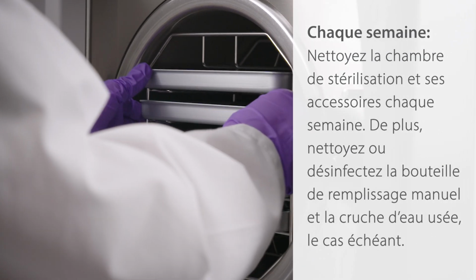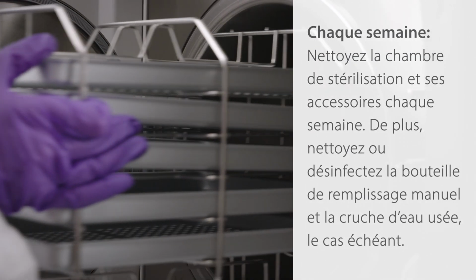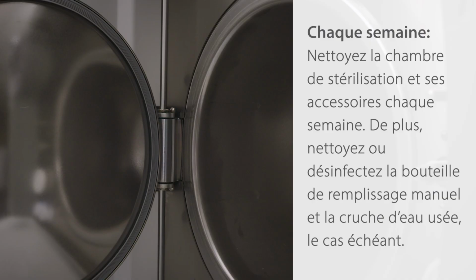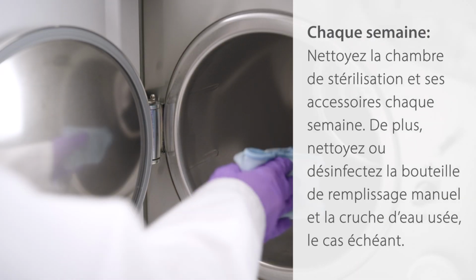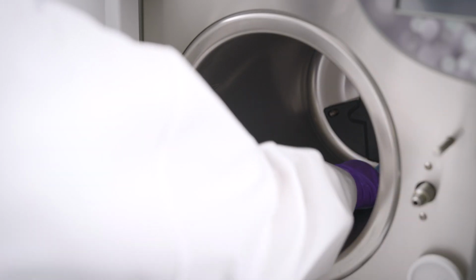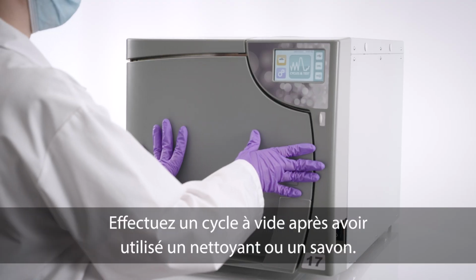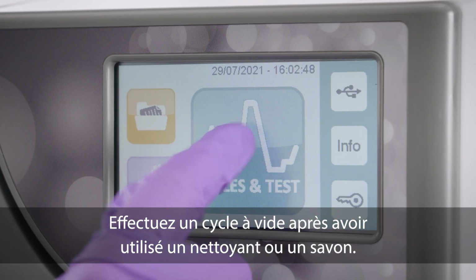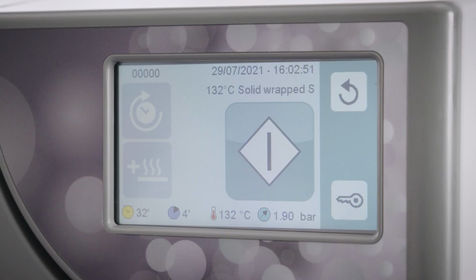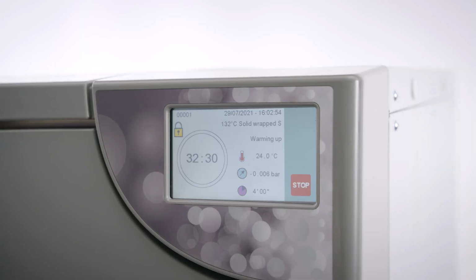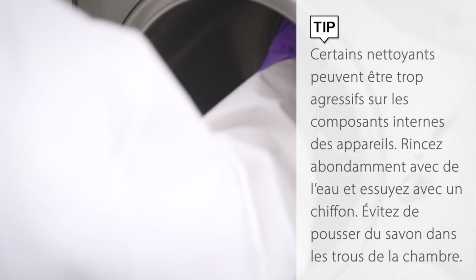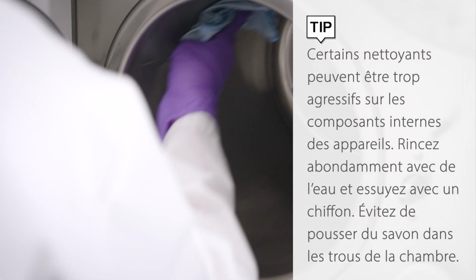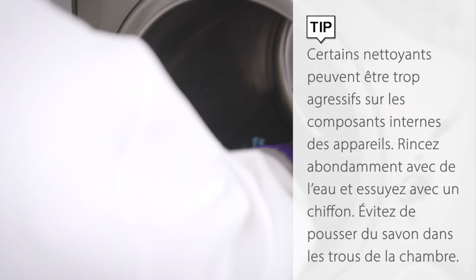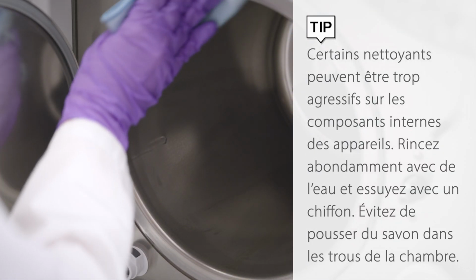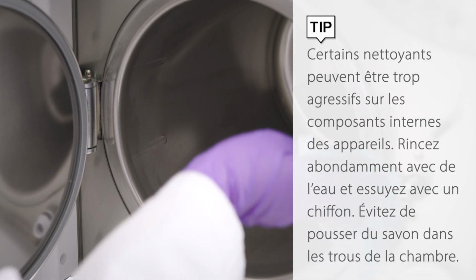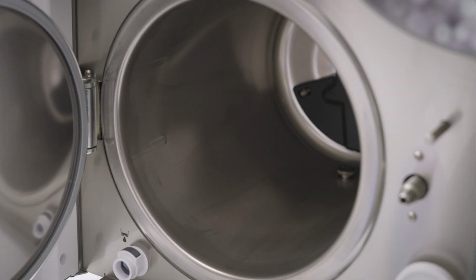Weekly. Every week, clean the sterilization chamber and its accessories. As well, clean and disinfect the manual filling bottle and the wastewater bottle if applicable. Run 1 empty cycle after using any cleaner or soap. Helpful tip: some cleaners may be too harsh on the internal components of the units. Rinse thoroughly with a cloth and water. Avoid pushing any soap inside the holes in the chamber.